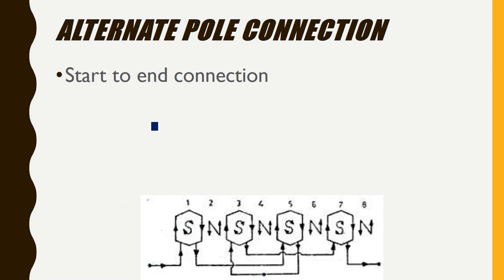So with this type of connection, a combination of alternate and adjacent pole connection, we can make pole changing motors, a motor with one set of poles that can be reconnected to another set of poles. A pole changing motor is used for two possible speeds. If 4 pole and 8 pole motors are used for speed variation, it can be running at 1500 rpm or 750 rpm.